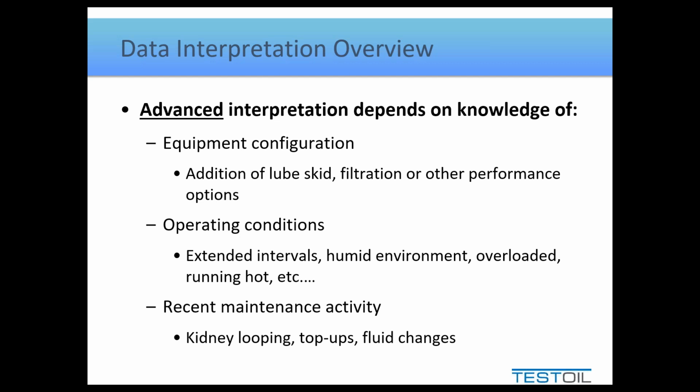They know at least three things the lab would never know. They know the equipment configuration, like does it or does it not have a filtration system? Where is it located? What's the environment around it? What kind of conditions does it have? Things like this. And they also know if there was any maintenance done recently, right? Was the oil changed? Was the bearing replaced? All these kinds of things. So with this kind of knowledge, they always have a bit of an ace up their sleeve to do a much, much better job at it than any lab would ever do.